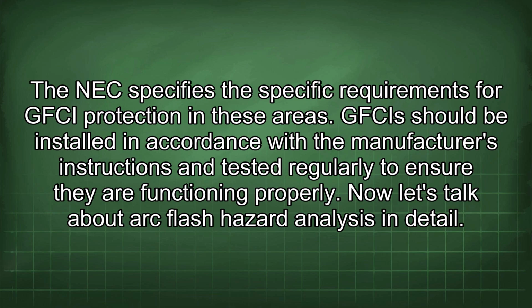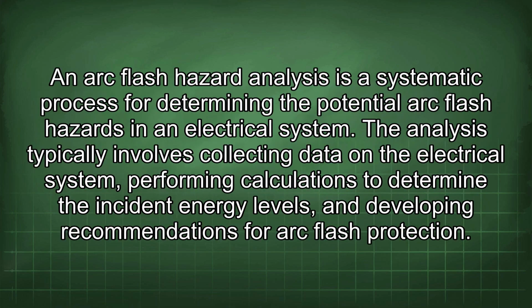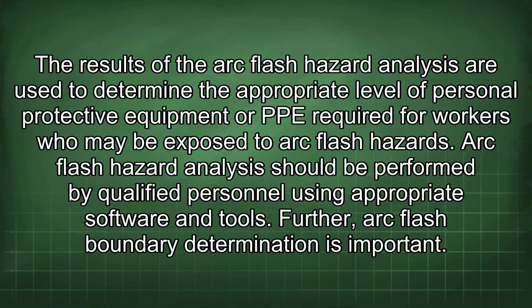Now let's talk about arc flash hazard analysis in detail. An arc flash hazard analysis is a systematic process for determining the potential arc flash hazards in an electrical system. It typically involves collecting data on the electrical system, performing calculations to determine incident energy levels, and developing recommendations for arc flash protection. The results are used to determine the appropriate level of personal protective equipment (PPE) required for workers who may be exposed. This analysis should be performed by qualified personnel using appropriate software and tools.